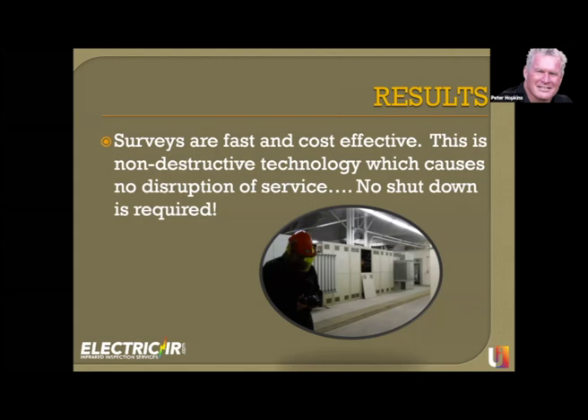This is an example where the client required us to be suited up. Some of the rules in thermography have changed — if you're beyond the arc flash zone, typically about 6 feet back, you don't need any of this gear. The gear is required for the electrician opening and closing the equipment. The risk is on the equipment when it's opened, not necessarily while it's open and I'm looking at it — the risk is low, unless you start hearing buzzing when you get near it. In that case, you stand back.